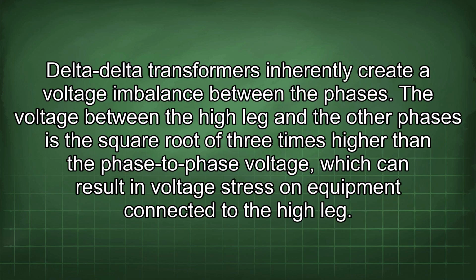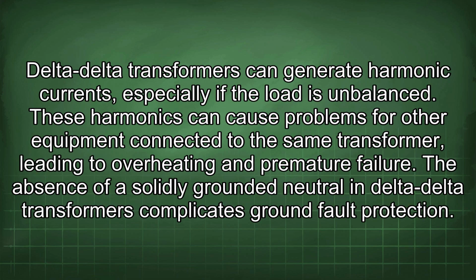Delta-delta transformers inherently create a voltage imbalance between the phases. The voltage between the high leg and the other phases is the square root of 3 times higher than the phase-to-phase voltage, which can result in voltage stress on equipment connected to the high leg. Delta-delta transformers can generate harmonic currents, especially if the load is unbalanced. These harmonics can cause problems for other equipment connected to the same transformer, leading to overheating and premature failure.